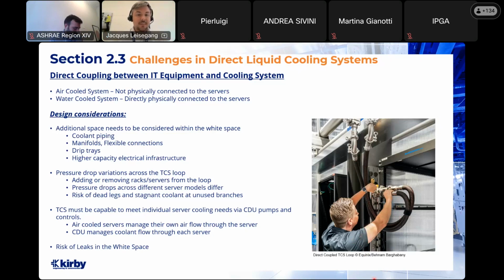With bringing your coolant piping into your white space, there's also a risk of leaks within the white space. So ensuring a robust leak detection system is in place is key. The coolants being used in the TCS will require a specialized and separated drainage and containment system. We can't have these coolants leaking into the environment or leaking into the typical stormwater drainage system. So having a specialized drainage and containment system is key, in addition to that leak detection system.